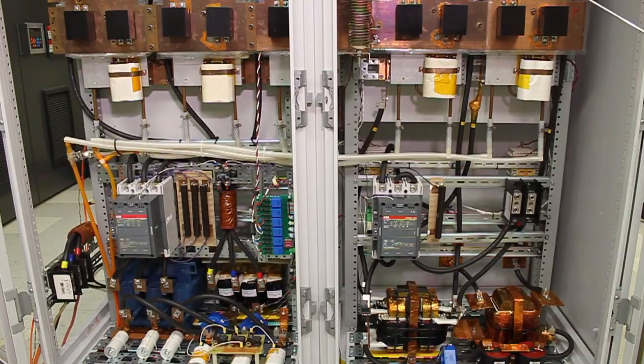The layout for the DC-DC power stage is similar to that of the DC-AC part. The integrated coupled inductor for the DC output is a very novel design to reduce the volume of the passive components. The common mode choke at the DC side suppresses the leakage current and avoids large transformers. There is also a pre-charge circuit at the DC side to establish the DC link voltage from the DC side.